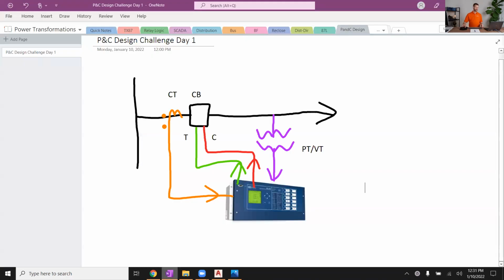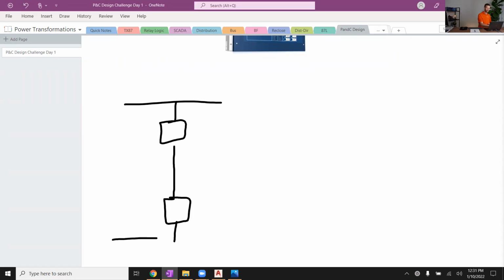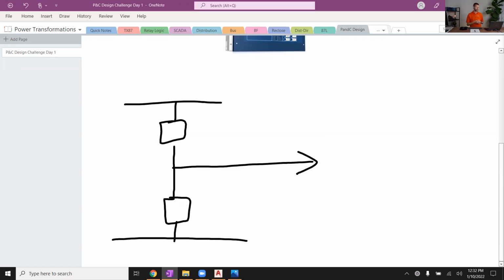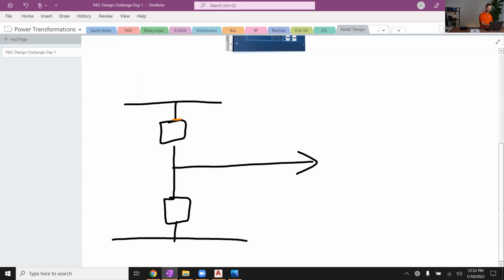I'll give you a quick whiteboard sketch of that in case you're not familiar with this. Perhaps you have a double bus, double breaker kind of architecture. Maybe I should specify that horizontal line this time is the bus 1 and bus 2. And then I've got these squares, breaker 1 and breaker 2. And then I'm going to have a transmission line terminated here between these 2 breakers going out to another substation. But what about the CTs in this case where we've got 2 breakers? I would have CTs on that breaker bushing and CTs on this breaker bushing. So now I've got 2 sets of 3-phase CTs.